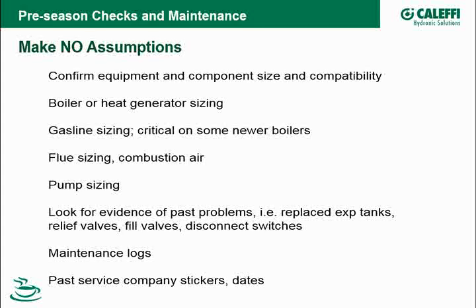And same thing with switches that might have been disconnected. I know when we did a lot of copper tube boiler, there'd be issues with the flame rolling out the front sometimes, and a service contractor that didn't understand what the true problem was tended to just disconnect or hotwire over the top of safety switches. So, again, just pay attention to what's been done in the past. Maintenance logs, if there isn't one there when you get there, that's a good thing to leave when you leave the job.